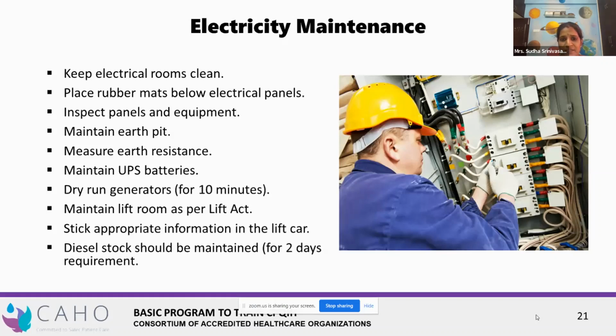Placing the rubber mats is very, very important. There is something called the 11 kV rubber mat, which is shock proof. Adequate PPEs for the people who are working inside the electrical panel rooms is very important, be it the gum boots or the ear mufflers for people working in the compressor rooms. So these are very, very important.